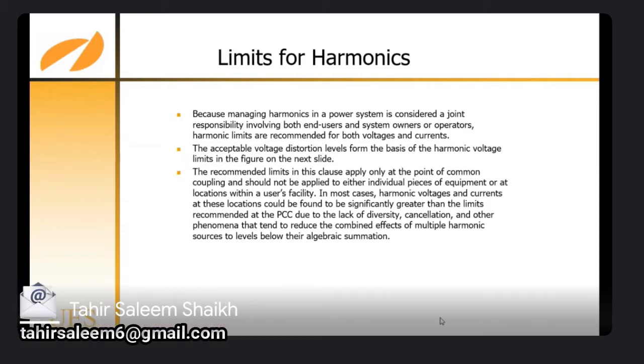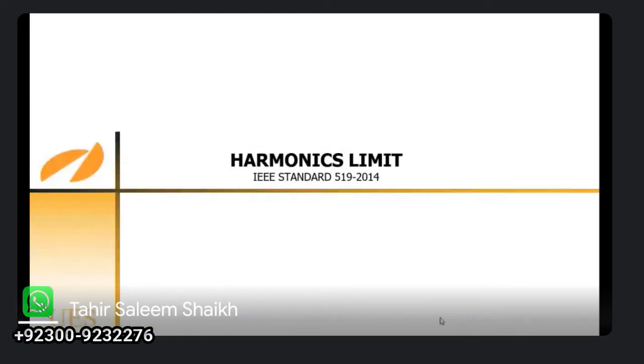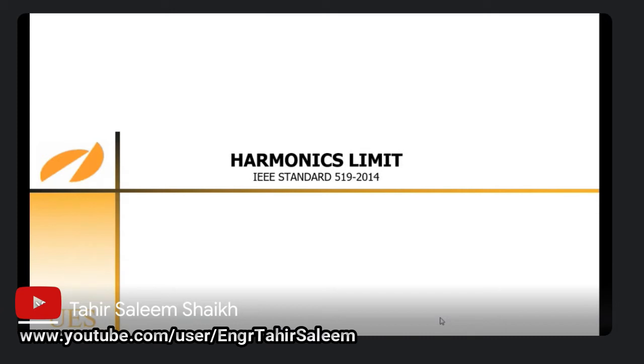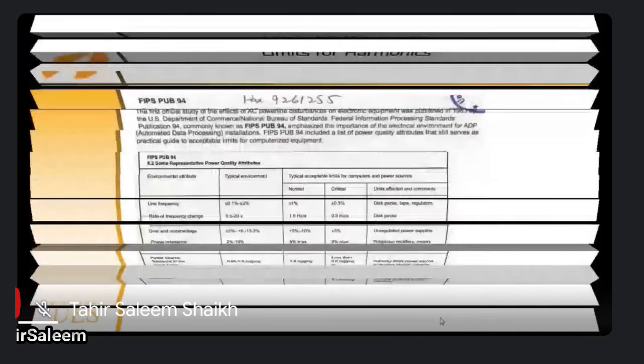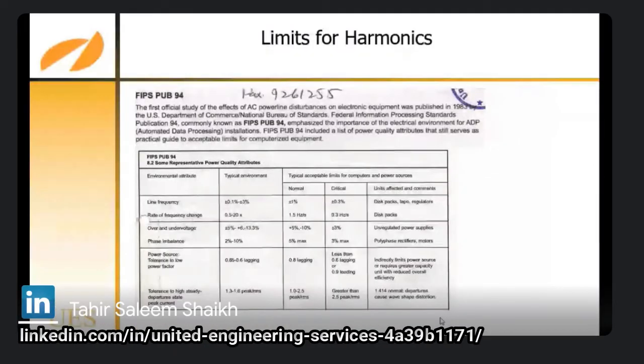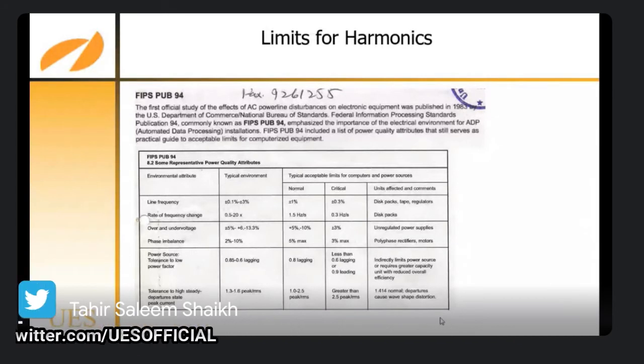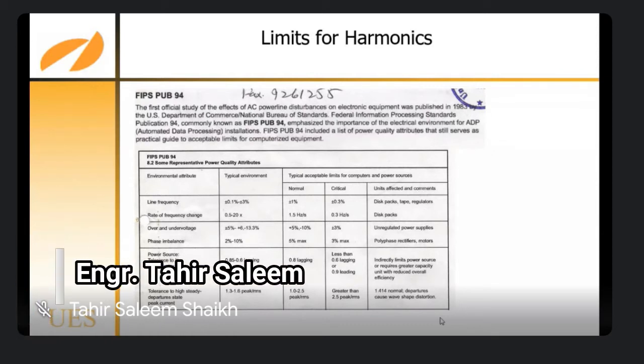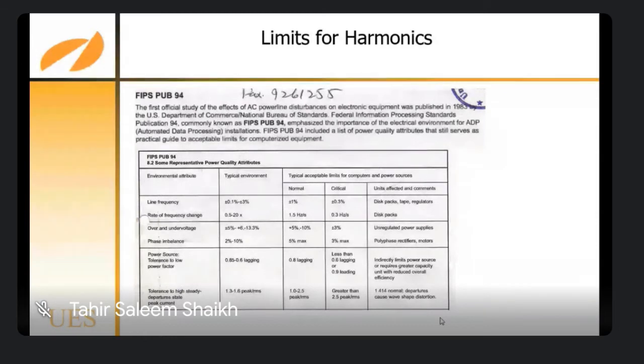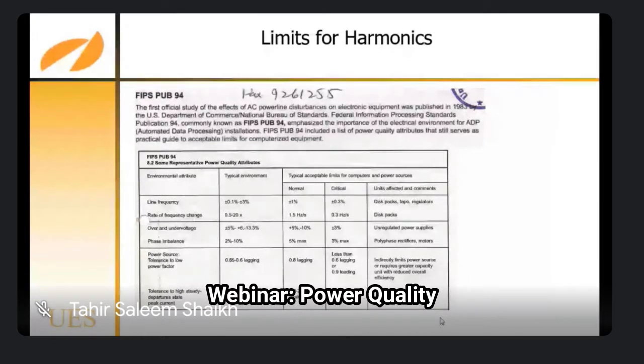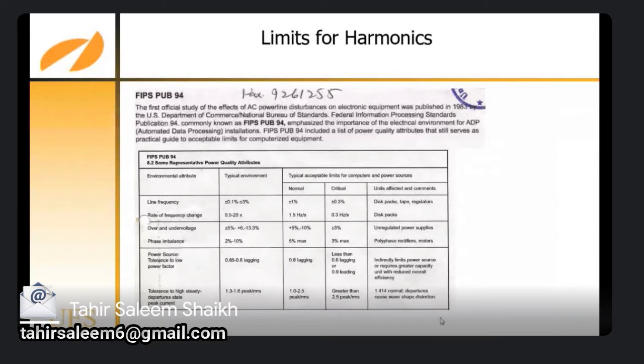Now, if we come to the standards, IEEE standard 519-2014 states that you can see over here, this is a chart which will give you some limitations. I found it in some publications. So the line frequency, there are different parameters, not only for harmonics, but for others also. The typical environment will be 0.1% to plus minus 3%. Typical acceptable limits is plus minus 1% for normal load, and critical load is plus minus 0.3% frequency deviation.